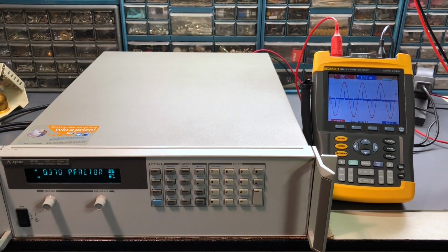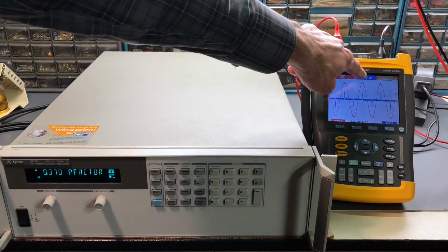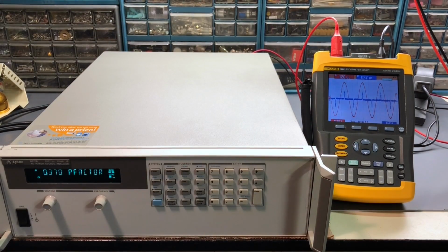It has very sharp spikes or peaks in the current waveform, and you can see those occur right at the high point on the sine wave for the voltage waveform. But it's not a very nice continuous current waveform like we saw with that incandescent lamp. Now you can see over here the power factor reading is 0.37. It's a very low power factor, and that's in agreement with that Scopemeter. You can see the power factor reading right up there, 0.37.